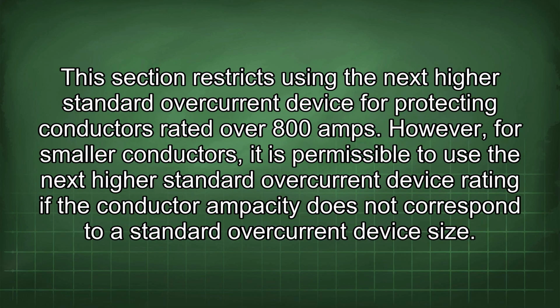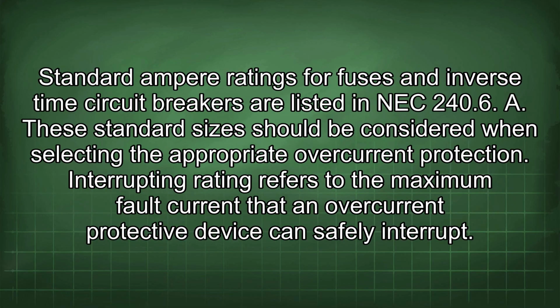This section restricts using the next higher standard overcurrent device for protecting conductors rated over 800 amps. However, for smaller conductors, it is permissible to use the next higher standard overcurrent device rating if the conductor ampacity does not correspond to a standard overcurrent device size. Standard ampere ratings for fuses and inverse time circuit breakers are listed in NEC 240.6(A).